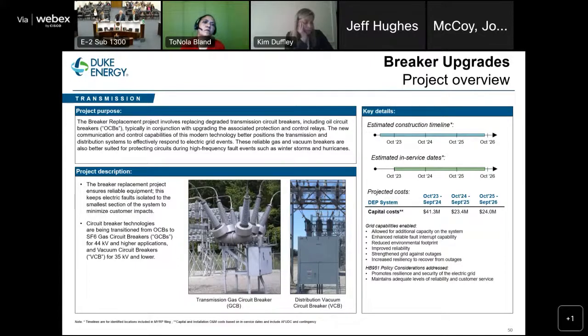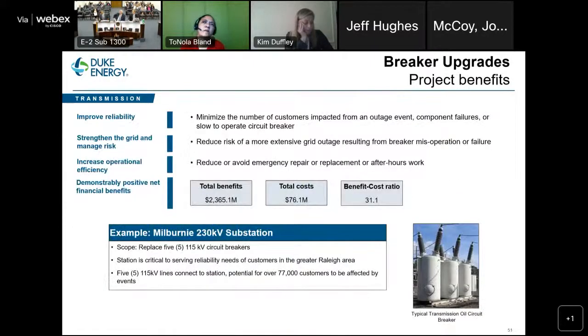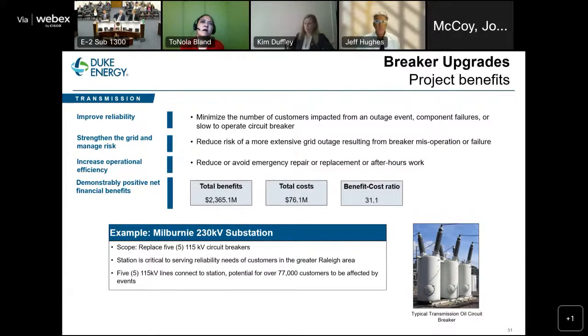One important factor with circuit breakers, and I alluded to this earlier, is that if a circuit breaker does not operate reliably to isolate a fault, the section of the transmission grid that isolates grows, right? The backup breakers need to operate. So this could be at remote substations, further out on transmission lines, at adjacent transmission stations, and therefore more customers are interrupted. So ensuring a circuit breaker reliably operates on the fault when given a signal to open is very important to minimize the impacts on our customers.